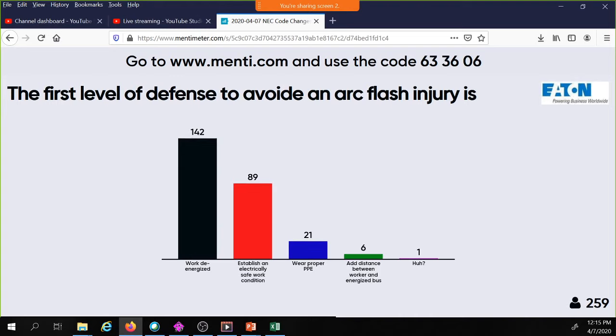And a part of establishing an electrically safe work condition are a lot of other things. You have to understand all of your sources of power. You have to do a lockout tagout program. You might have to put ground straps in, temporary grounding for safety. So it's not enough to say work de-energized. You have to follow the 70E guides for establishing an electrically safe work condition, which is a lot more than just working de-energized.